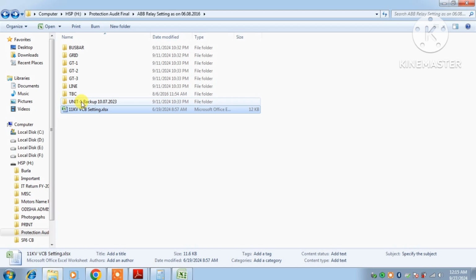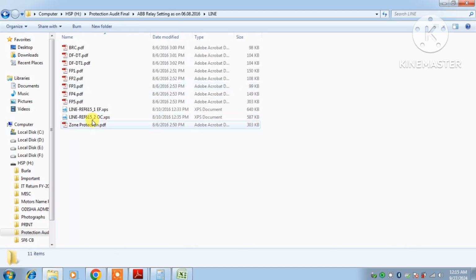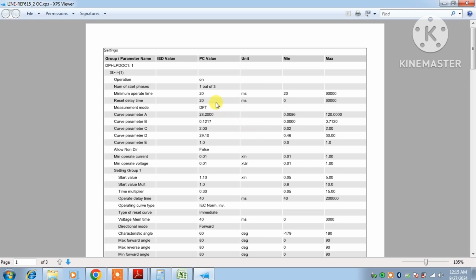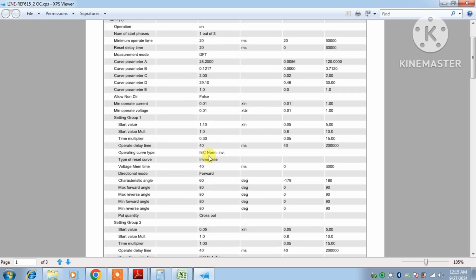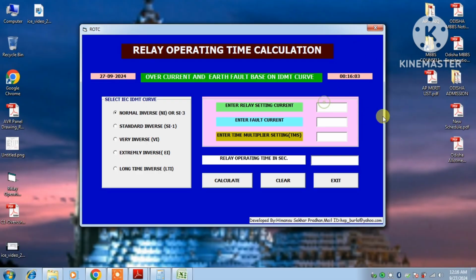Suppose one more, a line relay, you can take one setting here. It is also an ABB REF 615 relay. In this relay also we can see the settings. The CT ratio we have taken as 300/1. This is the curve we can see, IEC normal inverse curve. And this is the start value, 1.10 times the setting current. The time multiplier, the TMS, is given as 0.30, and the curve selection is IEC normal inverse. So accordingly we can also calculate it, whether taking the primary value or the secondary value. Provided we enter a numeric value in the cell. Second, the fault current should be higher than the setting current.